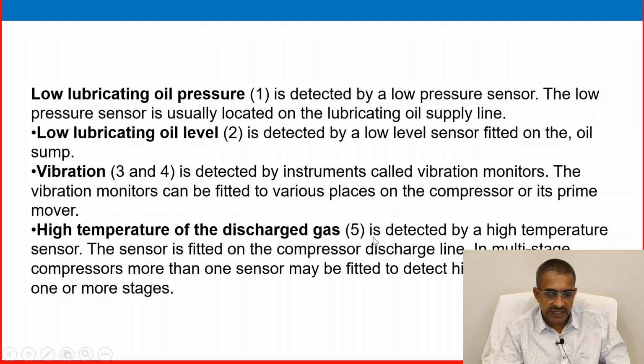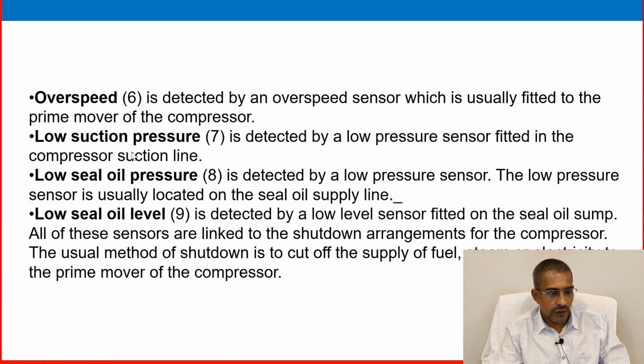High temperature of the discharge gas is detected by a high temperature sensor. The sensor is fitted on the compressor discharge line. In multi-stage compressors, more than one sensor may be fitted to detect high temperatures from one or more stages. And overspeed is detected by an overspeed sensor, which is usually fitted to the prime mover of the compressor. Low suction pressure, another trip condition, mainly a trip condition, is detected by a low pressure sensor fitted in the compressor suction line. Low seal oil pressure, another one. Earlier we discussed lube oil pressure. Here it is seal oil pressure and seal oil level, that is also there.